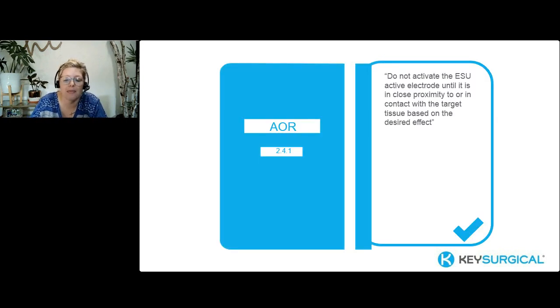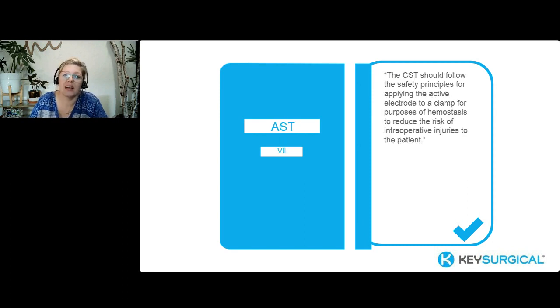So kind of to support this, AORN says don't activate the ESU until it's in close proximity or in contact with the target tissue for the desired tissue effect. AST says the CST should follow safety principles, and this is kind of that when we do it on purpose, when we do direct coupling on purpose. AST says you probably shouldn't do it, you might have to do it, so here's kind of how to do it safely. They have some really good guidelines for best practice and also a little bit of those realities, right?